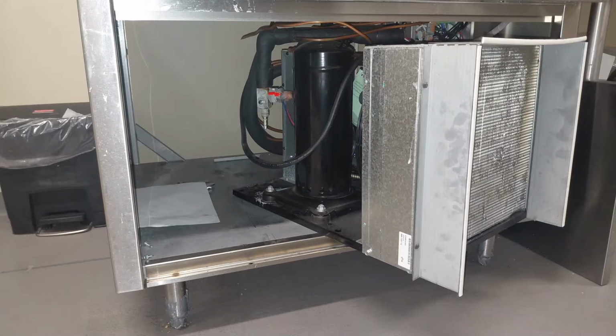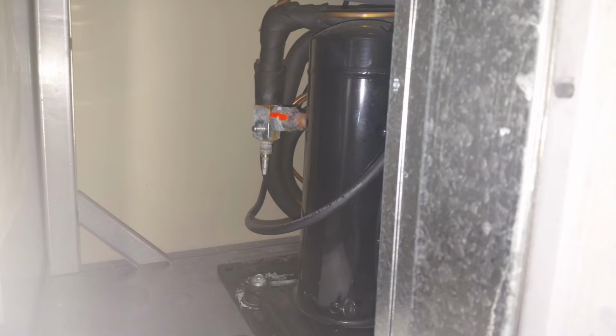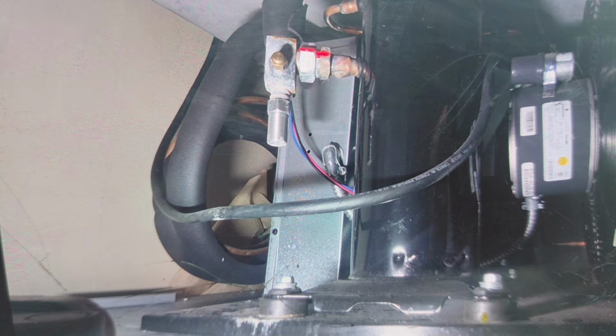So when this happens to a scroll, it internally bypasses and the discharge gas rushes down the side of the compressor into the crankcase, and it causes it to go out on thermal overload in just a matter of minutes. So this scroll is getting replaced. It's getting new starting components, a new plug, and I think a couple other things, a new dryer. It also needs a rotolock fitting for the suction. And that's it.